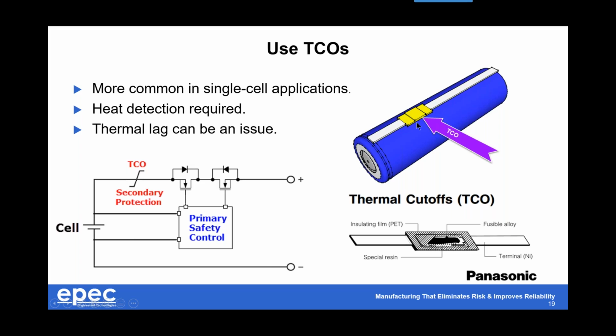We have actually passed UL 2054 using this method, and it worked quite nicely, and we stayed well within the low temperatures of 170 C. And 170 C, just for background, that is the surface temperature. The internal temperature is much higher. There's a phenomena within lithium-ion cells: if you exceed a certain internal temperature, you'll get into a thermal runaway. That thermal runaway could be very devastating, because the cell will take off and start firing. You've seen videos online about that, and you can't put it out. That's why they picked that 170 degrees C limit.